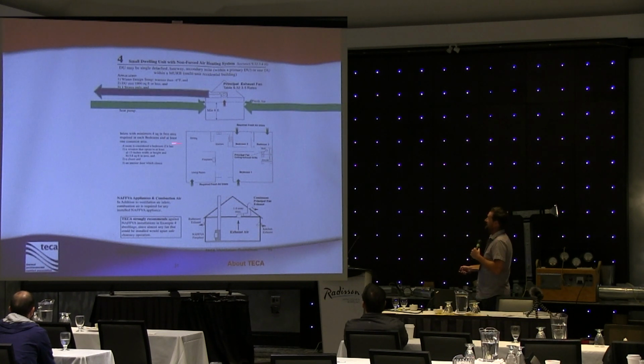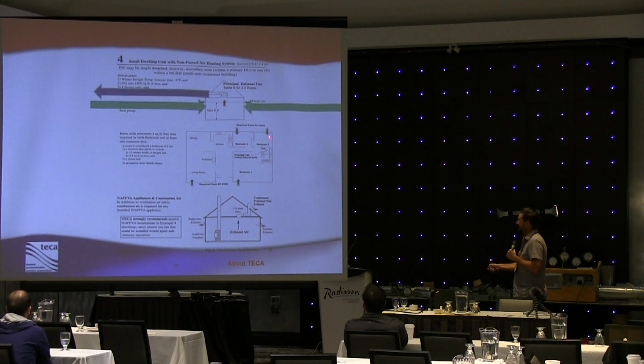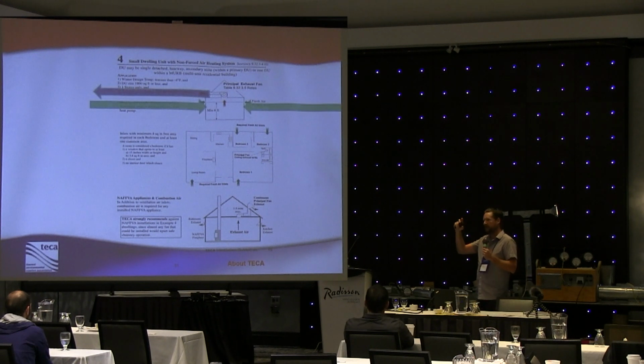All it is, it's 1 air inlet into each bedroom, and that air inlet has to have a minimum of 4 square inches of free area. That means that's the total opening that we can see through. It has to be 4 square inches. And it allows that fresh air to migrate directly into those bedrooms.